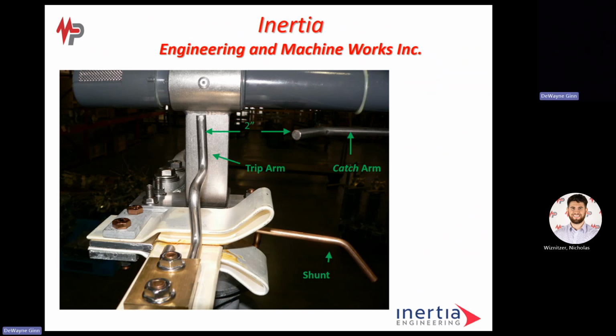The jaw itself, if you look at the color of it, is silver plated. The blade, which goes in the jaw, is silver plated. It helps cut down on resistance as well as corrosion. We use a shunt, which could be called an arcing horn, and we use a trip arm off the blade and a catch arm on the interrupter. There's a 2-inch gap right there. When I come out of the jaw with the blade, it transfers the energy load onto the shunt, and then transfers the trip arm to the catch arm before making the interruption. So I never have an arc in between. It's very important all the way around. These are air brake switches, but you don't want to have an arc burning.